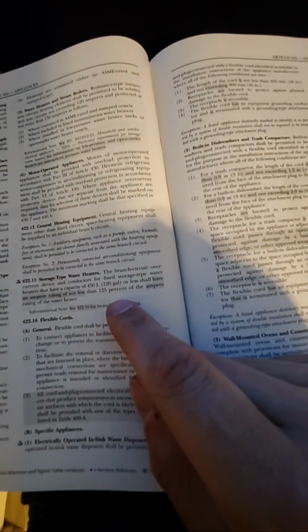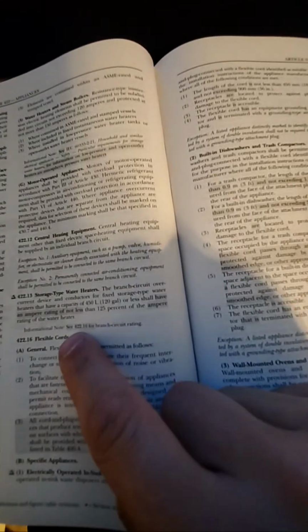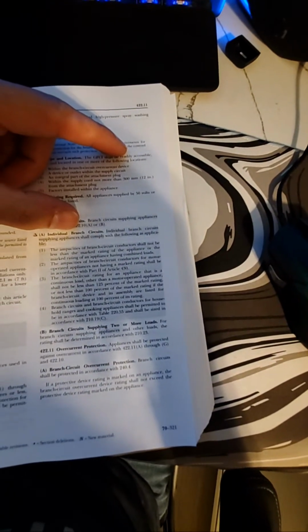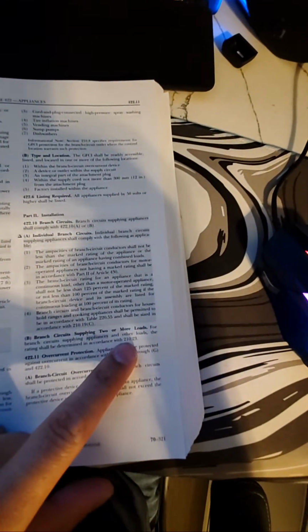So if we had looked just a little bit longer, we could have seen the branch circuit rating there. And we would have seen that when you size at 125%, typically that means it's going to be a continuous load. So if we went to 422.10, we would see here that we would have sized it as a continuous load. Yep. See here.